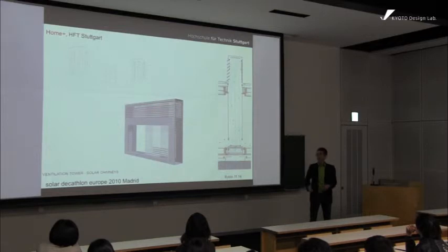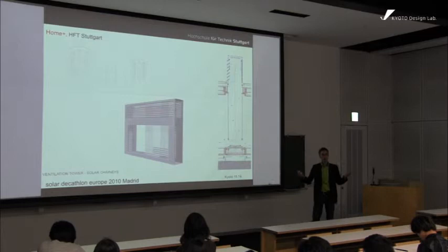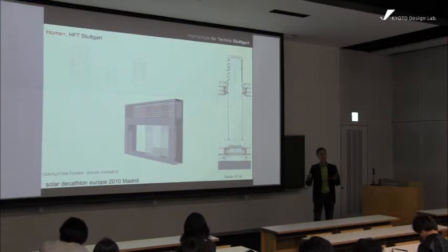The wind comes inside, and here we have an evaporative element. In this case, a metal mesh with water. You bring in water, and the water goes down and evaporates into the air. So the air has a temperature, let's say, 32 degrees and a humidity of 60%, and here the air has a temperature of 25 degrees and a humidity of 90%. So we use evaporative adiabatic cooling to cool down the fresh air.